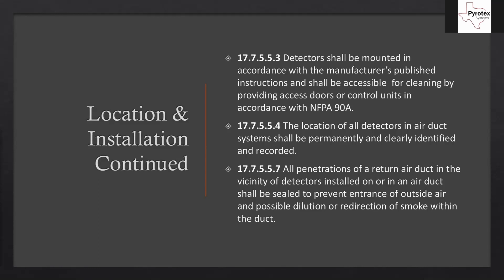The location of all detectors in the air duct system shall be permanently and clearly identified and recorded. This means as-built drawings must show exactly where the duct detectors ended up. On initial design I try to get close using mechanical drawings, but things change during construction — units get moved. If the duct detector had to go in the hallway outside the mechanical room instead of inside it, that needs to be reflected accurately on the as-built drawings.